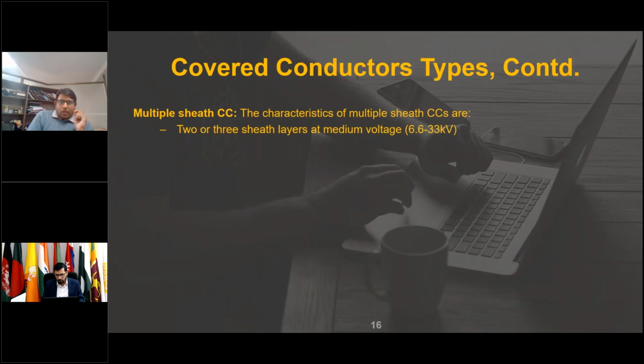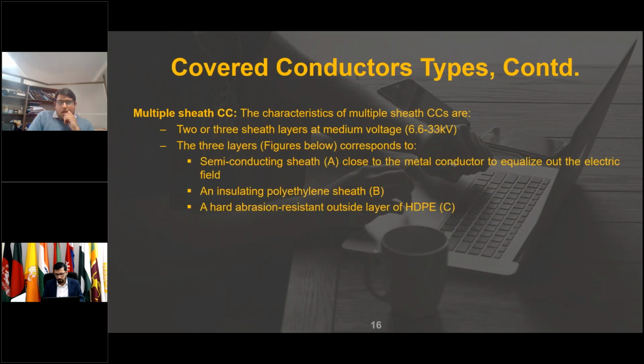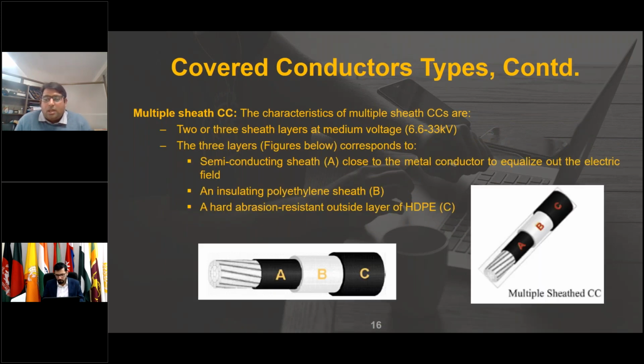Now we will move to the multiple sheath covered conductor, which is also known as the ABC conductor or multiple sheath conductor because it has three layers. There are two or three sheath layers at medium voltage, which ranges from 6.6 to 33 kV. The three layers, whose figures are shown below: if you refer to the A designation, it is the semi-conducting sheath close to the metal conductor to equalize the electrical field. Above A, there is an insulating polyethylene sheath designated as B, and above that there is a hard abrasion-resistant outside layer of HDPE designated as C.